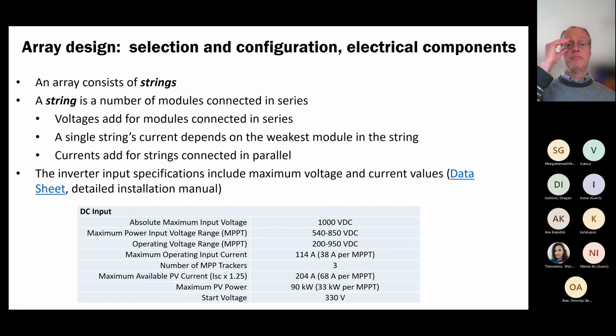Okay, so it turns out that each of these inverters has 3 of these maximum power point trackers. Those will adjust the current and the voltage at any given time to optimize the amount of power produced, because power ultimately translates to maximum energy, and that's the goal of any solar array. You can see there's also a minimum starting voltage. So when the sun is coming up in the morning and you start to get a little bit of light on the array, it's pretty quick. The voltage rises pretty quick at low light intensities. So the array will start pretty early, even when it's generating relatively low power.